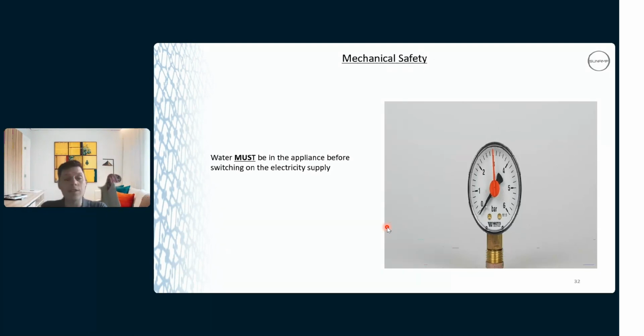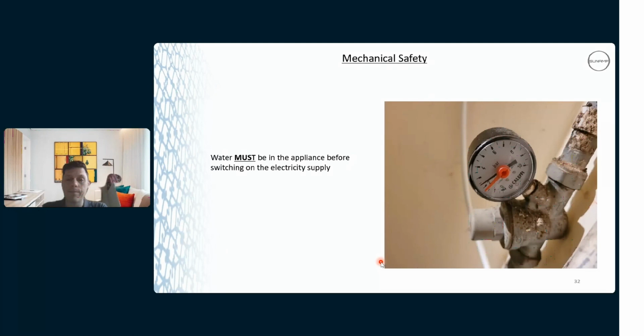Our heat exchanger must be pressurized with water before turning on the electrical supply. You might get the scenario where the sparky will go in, do his work, turn it on just to test it, which you want to do anyway, but he'll maybe get distracted, or leave it on by mistake, and then the plumber comes in a couple of days later and it's roasting hot. It can actually damage the heat exchanger and make it overheat. Don't get me wrong, you probably want to turn it on for a couple of minutes just to make sure your wiring and everything's correct and the unit is working, but just always make sure you turn it off. Ideally, just make sure the water's in the heat exchanger before turning on the electrical supply - that's the right way to do it.